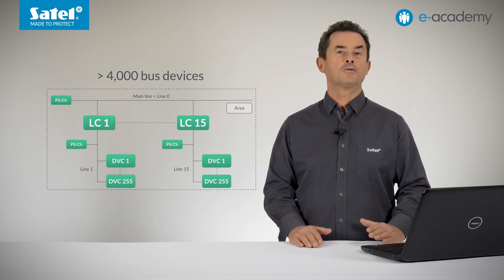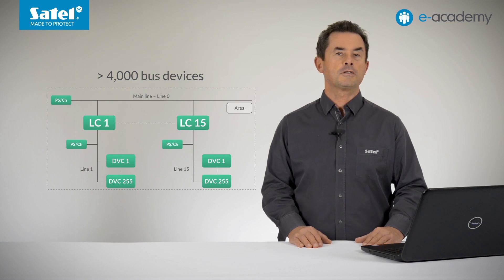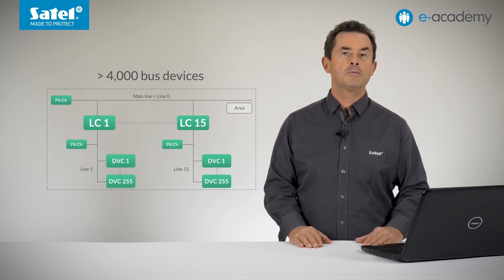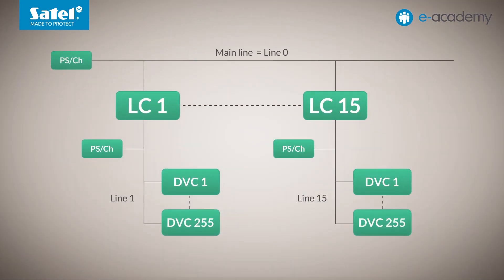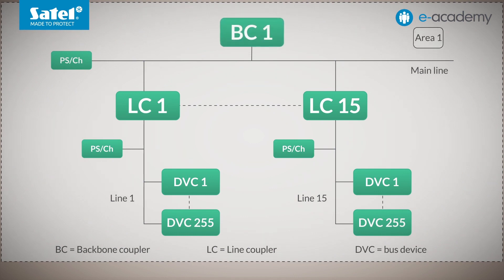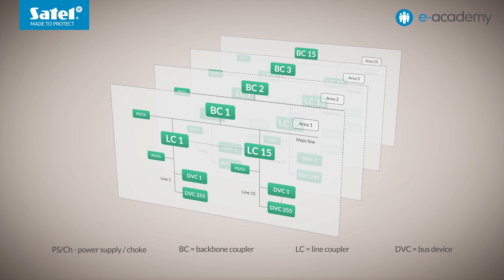What about the situation of very complex KNX installations intended to operate, for example, in a large office building, a public building, or a large hotel? Obviously, it will become necessary to extend the structure. Backbone couplers can be installed on a so-called backbone line, with which up to 15 areas can be connected to it. In addition, up to 256 devices, including couplers, can operate on a backbone line, as on the previously discussed lines. This line also requires its own power supply. As a result, more than 61,000 devices can be installed across the entire KNX-TP network.